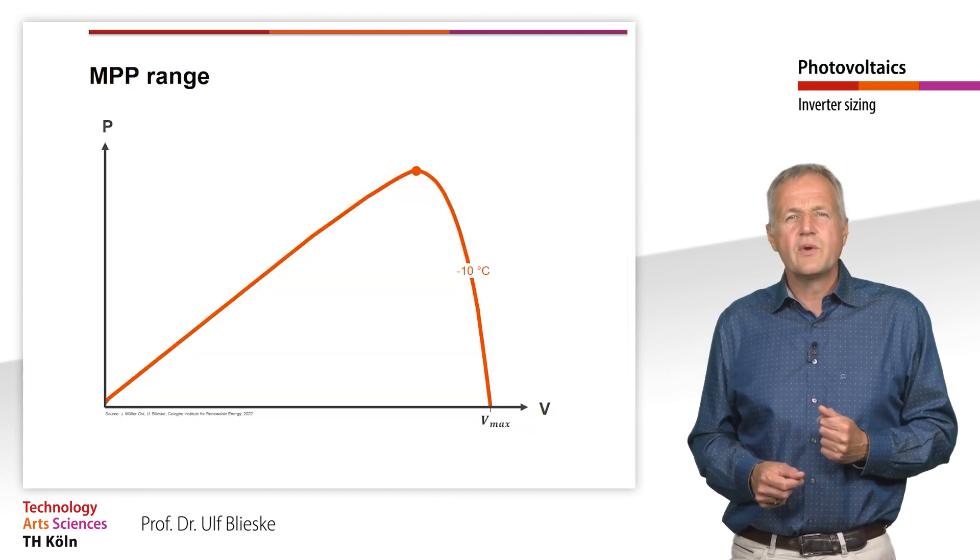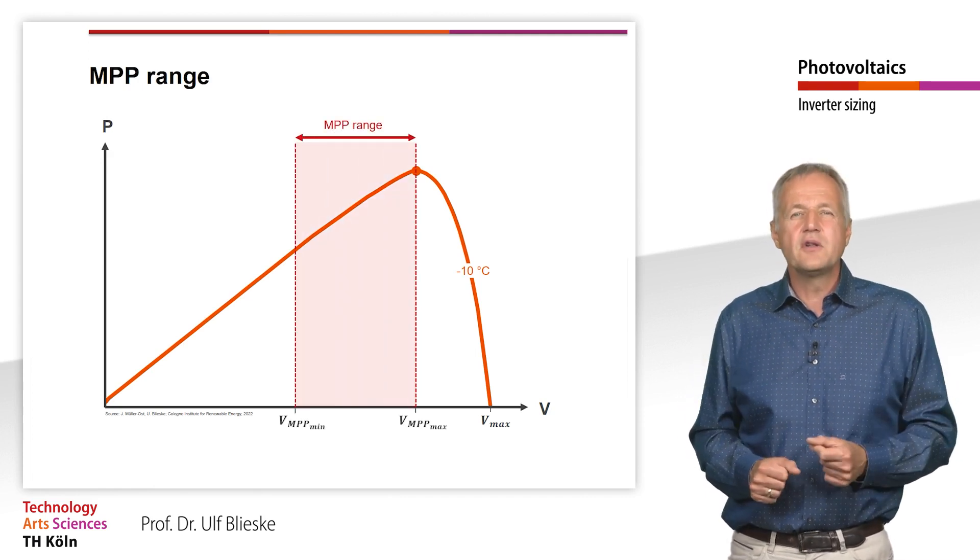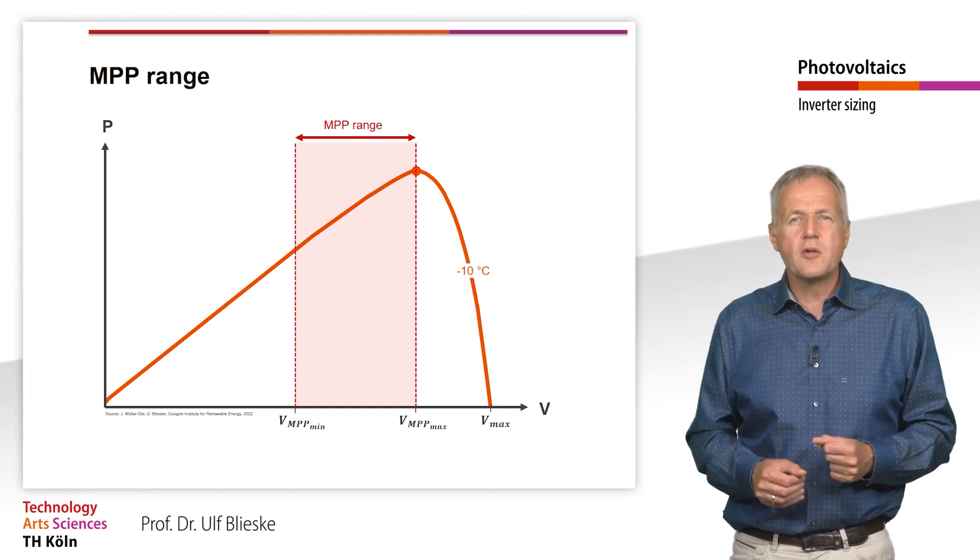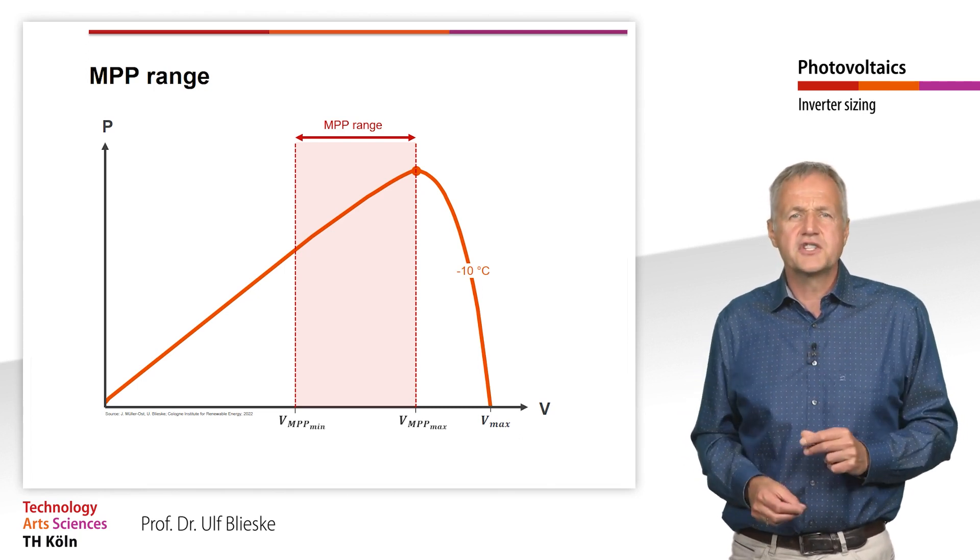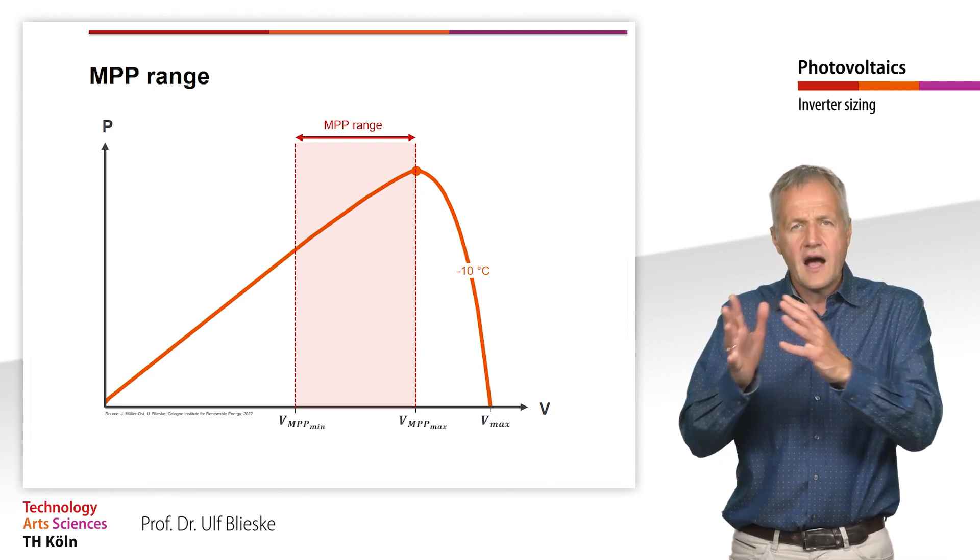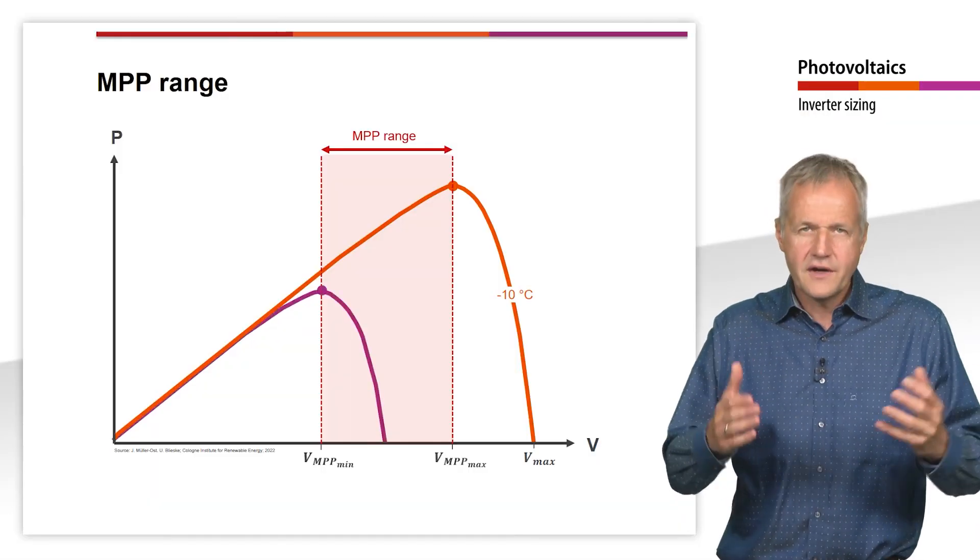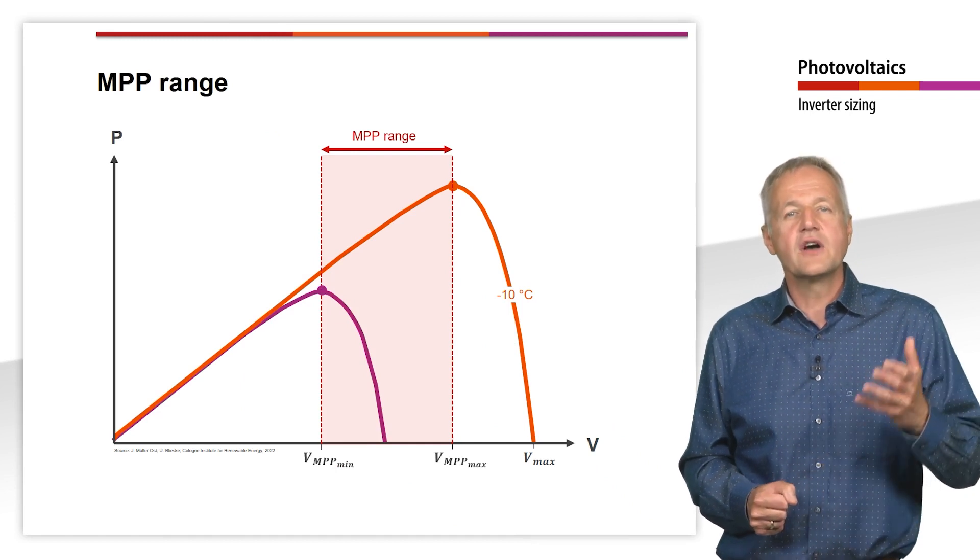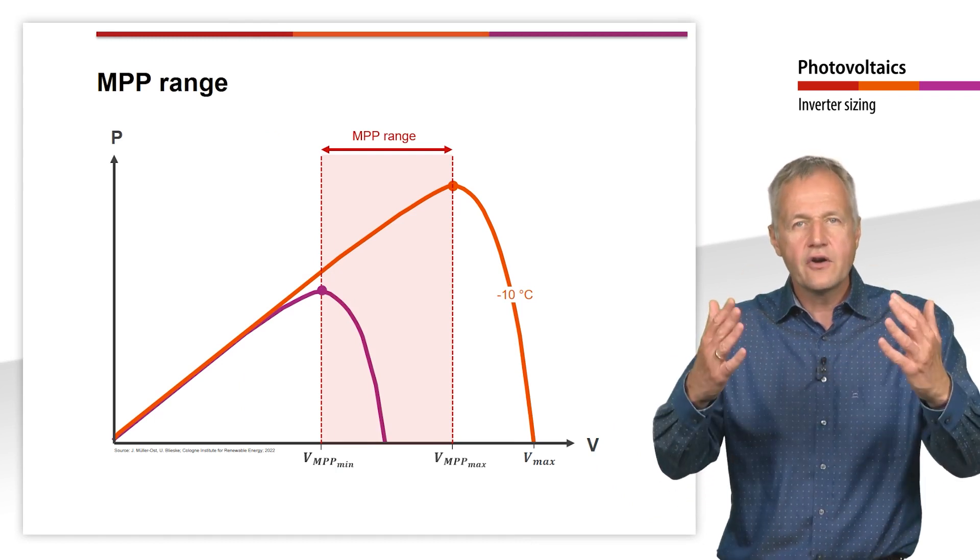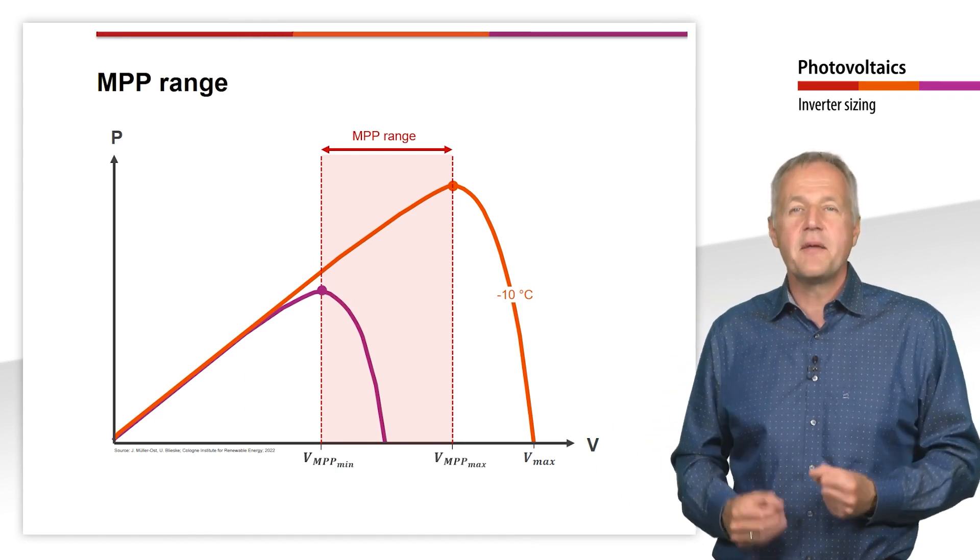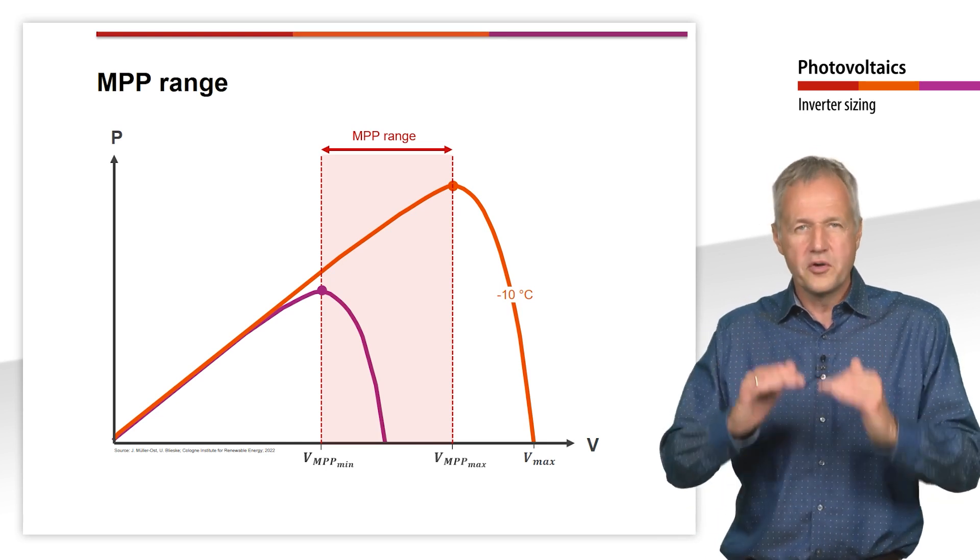The next sizing condition we will deal with is the MPP tracking range of the inverter. If possible, the inverter should be able to set the optimal operating point at the generator even in extreme situations, that is, at very high or at very low MPP voltages. In contrast to the last criterion, however, the inverter will not be damaged if the generator voltage should be somewhat higher or lower since the MPP voltage is inevitably always lower than the open circuit voltage.